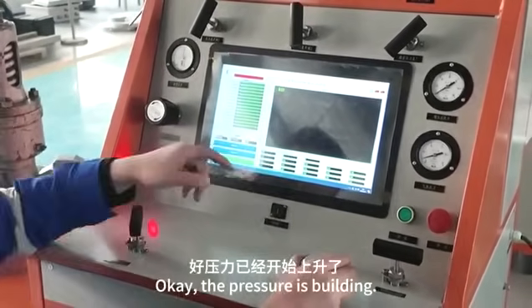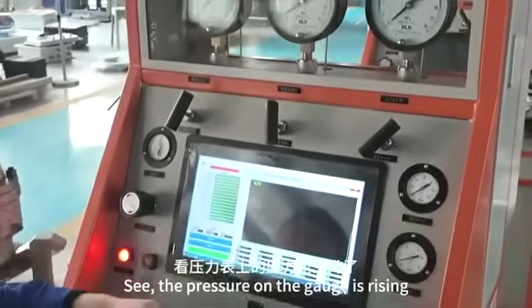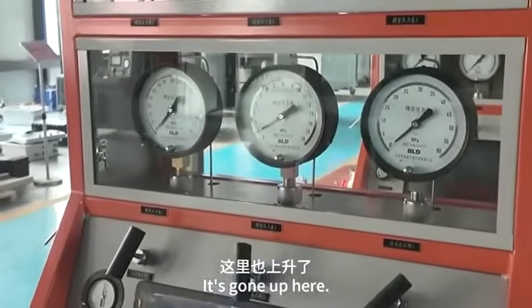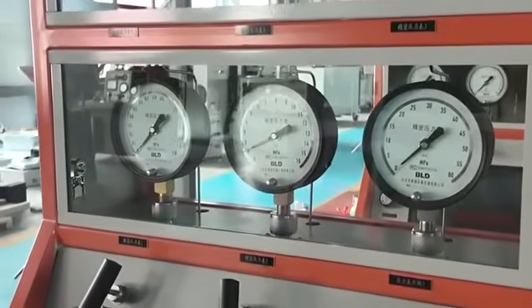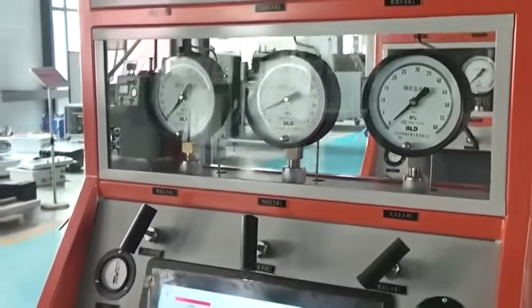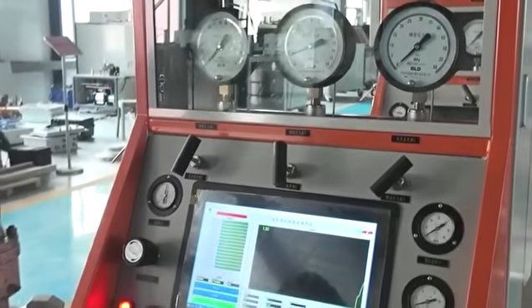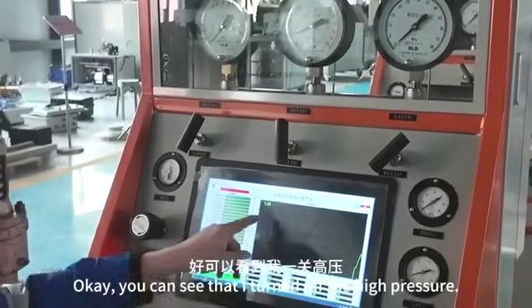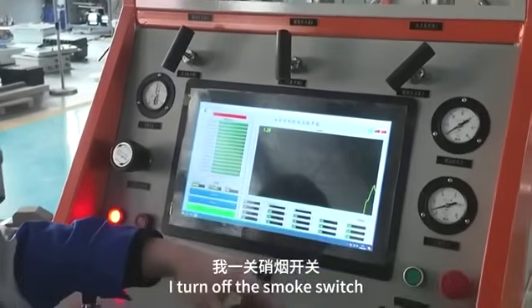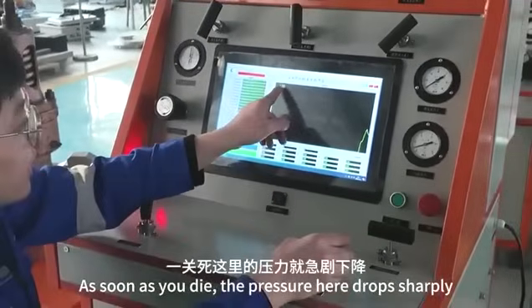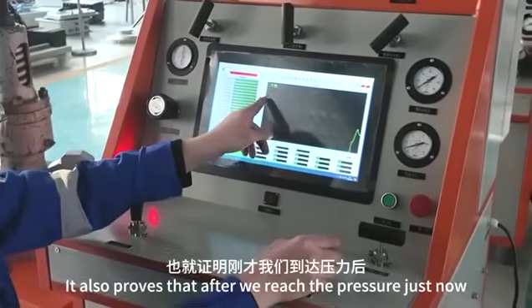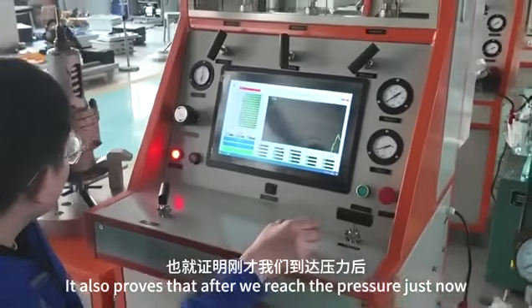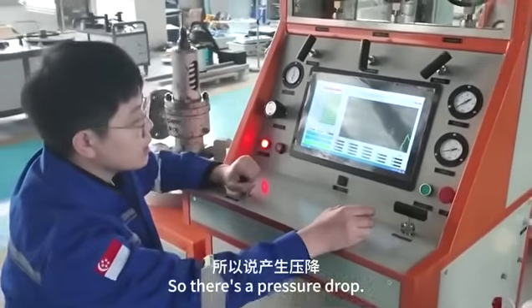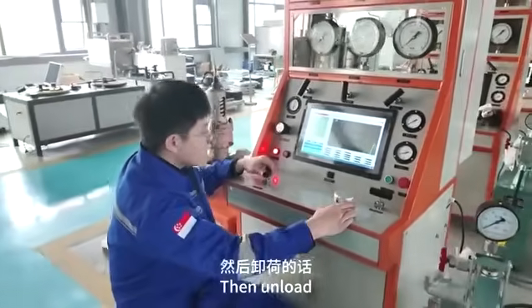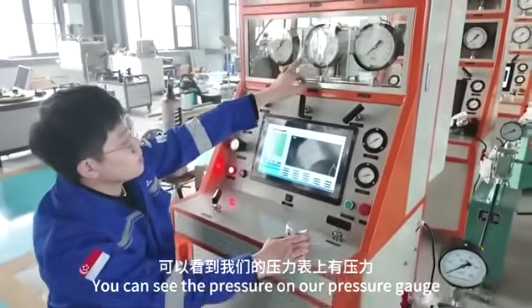Okay, the pressure is building. See, the pressure on the gauge is rising. It's gone up here. We slowly boost the pressure. Okay, you can see that I turned off the high pressure switch. As soon as I close it, the pressure here drops sharply. It also proves that after we reached the pressure just now, the safety valve opened, so there's a pressure drop. Then unload. You can see the pressure on our pressure gauge.